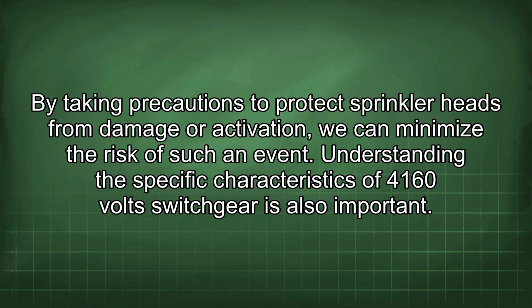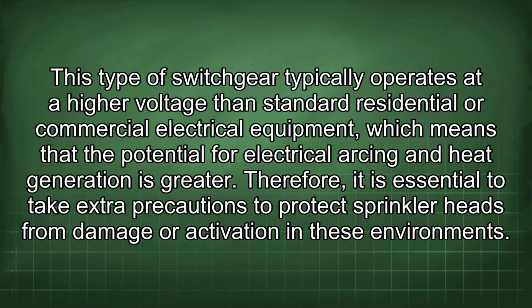Understanding the specific characteristics of 4160 volt switchgear is also important. This type of switchgear typically operates at a higher voltage than standard residential or commercial electrical equipment, which means that the potential for electrical arcing and heat generation is greater. Therefore, it is essential to take extra precautions to protect sprinkler heads from damage or activation in these environments.